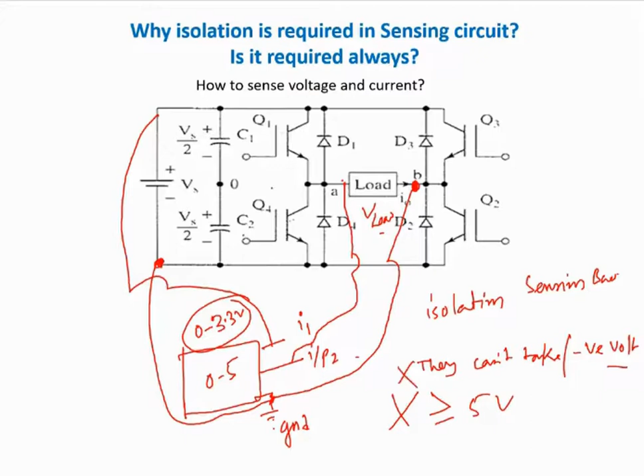For example, this is a current sensing arrangement. There is a hole in this, so you pass the wire whose current you want to sense. Principally it is a kind of current transformer. On the secondary side, you get step up or step down current as per requirement. That current you drop in a resistance, which gives you some voltage based on the resistance value. Then you feed it to some sort of op-amp circuit so that you can adjust the gain.